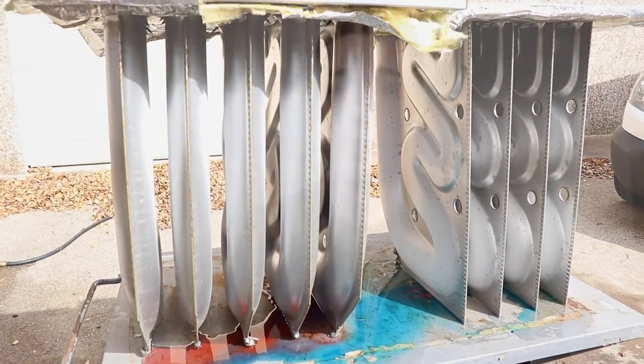There's no telling what it may look like 6 months or a year down the road compared to today. So the moral of the story is, if your HVAC guy comes in and waves around a carbon monoxide detector inside the house and doesn't pick up anything, that does not mean your heat exchanger isn't cracked or breached. It should be tested properly.